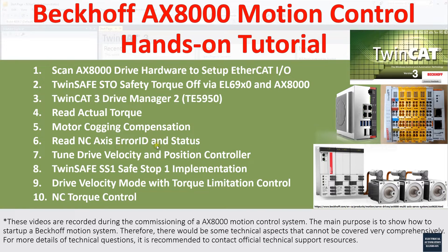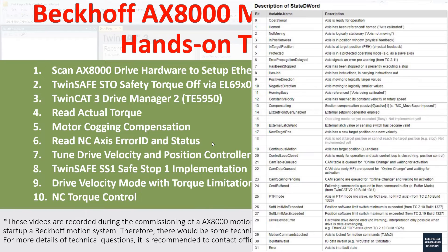Basically we can use the error ID and the status of this axis to diagnose what's going on with our drive, so we can troubleshoot. We can also prepare this error ID to show on the HMI display, picking a couple of important indicator or boolean signals from this status so operators or the maintenance team can quickly diagnose what's happening with the drive.